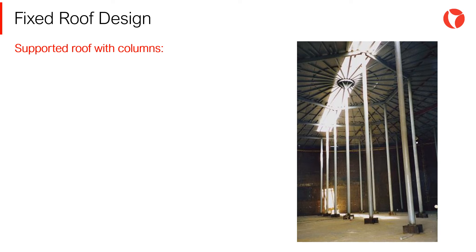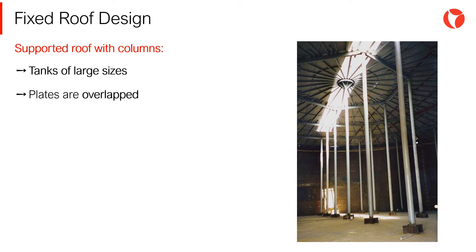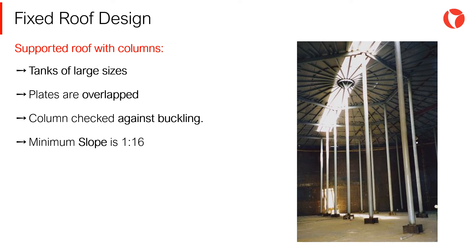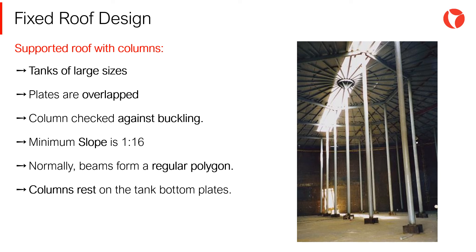The main characteristics of supported roofs with columns are: they are used for tanks of large sizes; the roof plates are overlapped and not welded to the structure; the columns should be checked against buckling according to section 5.10.3.4; the minimum slope of the roof will be 1:16; normally beams form a regular polygon or circles; and columns rest on the tank bottom plates.